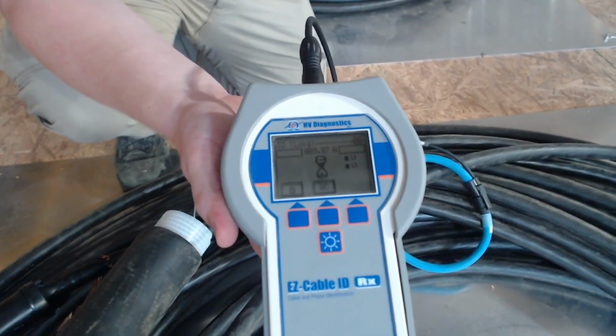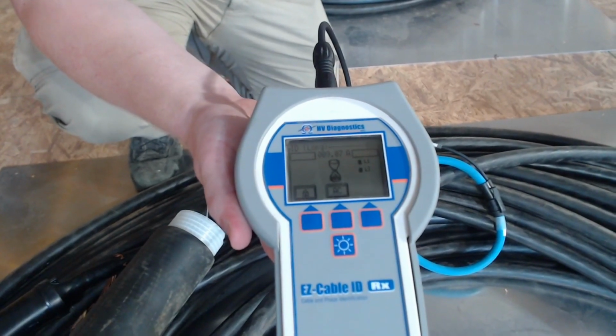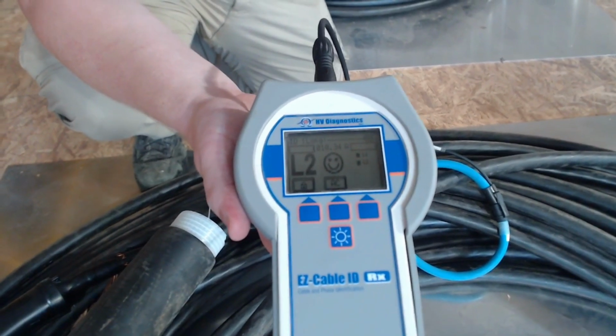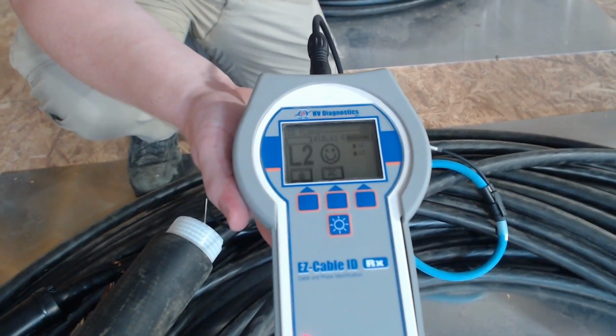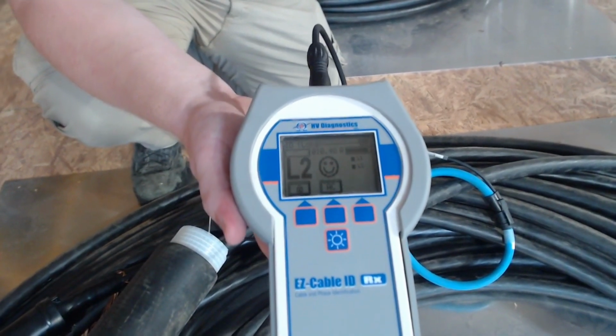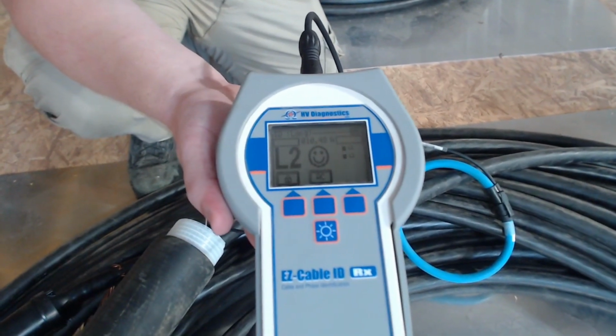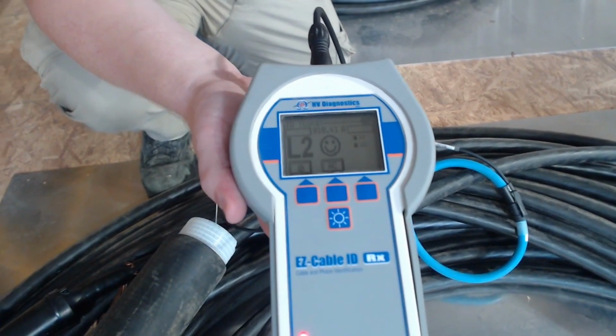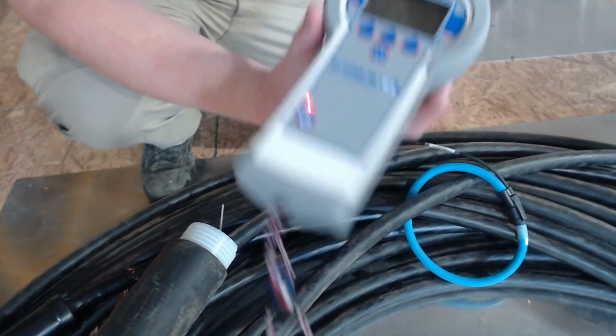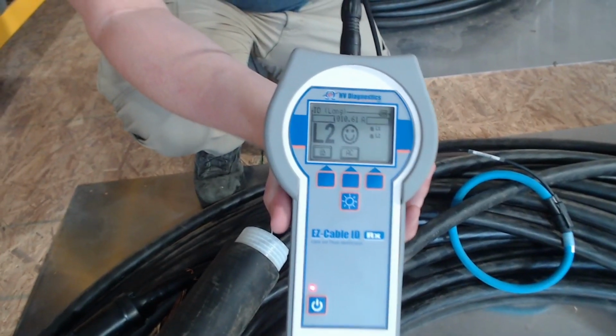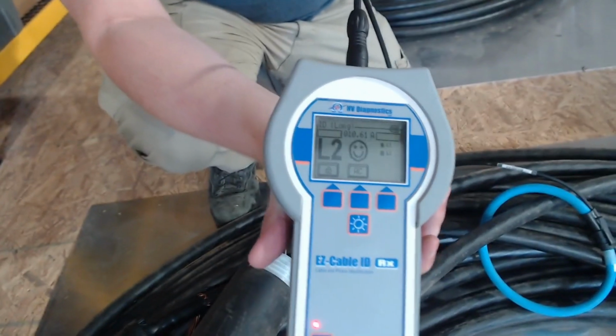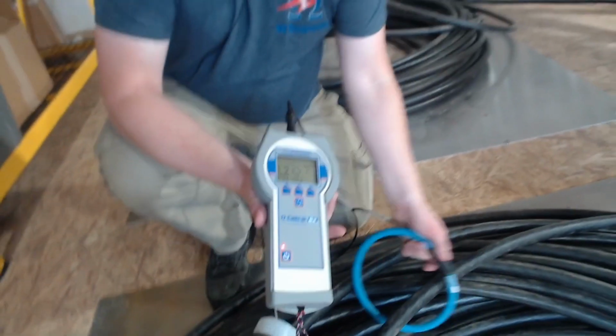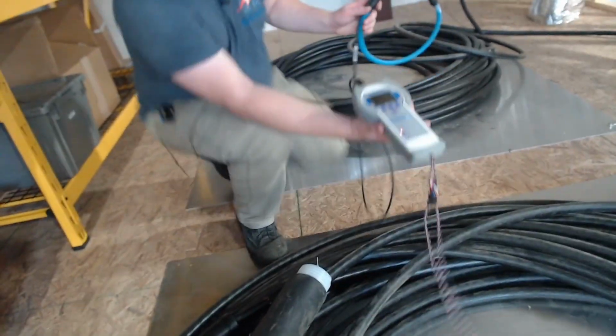And as it's identifying, we should see, yep, L2 smiley face. So the smiley face indicates that we have at least 65% of the current that we measured down at our calibration phase. So right now we're getting 10.1 amps, so that's about what we got with our calibration phase, so perfect. So now we move over to our third phase.